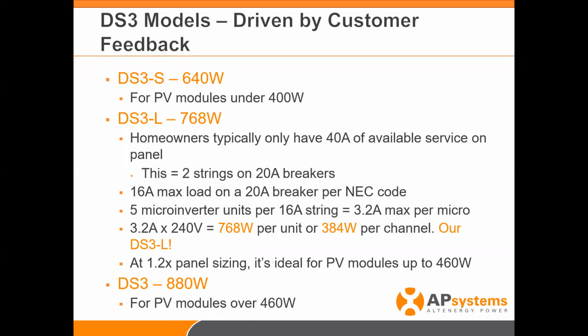So one of the ways that we did that is we noticed that on a typical residential installation, there was about 40 amps of service available on a 200 amp panel, sometimes 60, but it usually was around 40 amps, ideal for 2 20 amp strings of microinverters. But the maximum you can load on a 20 amp breaker is 16 amps per NEC code. So we were able to design the microinverter so that we could maximize it with 5 microinverters per string, which came out to 3.2 amps per unit. At 240 volts, it was exactly 768 watts.